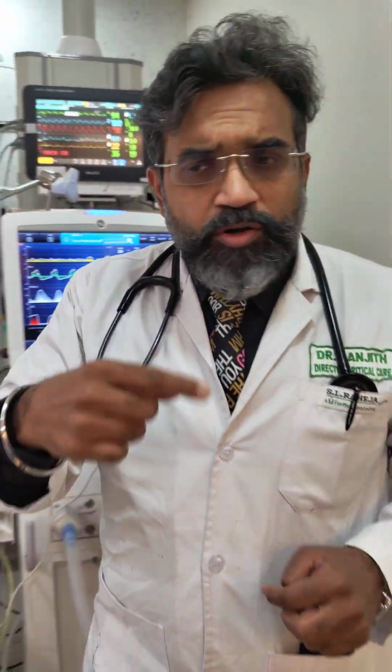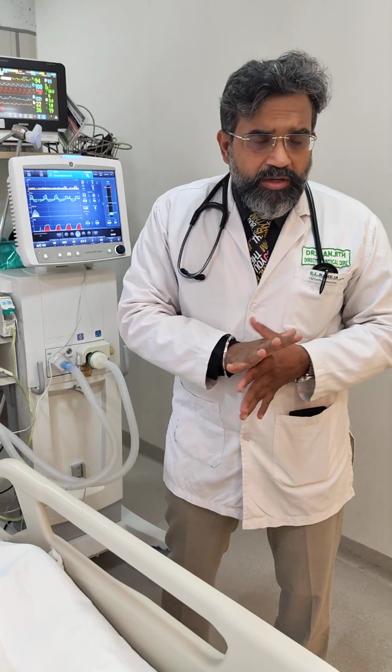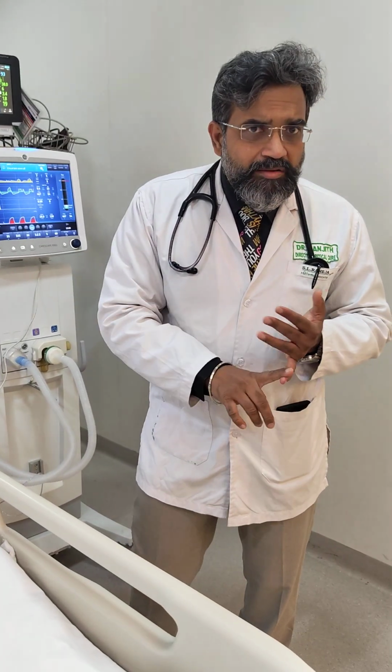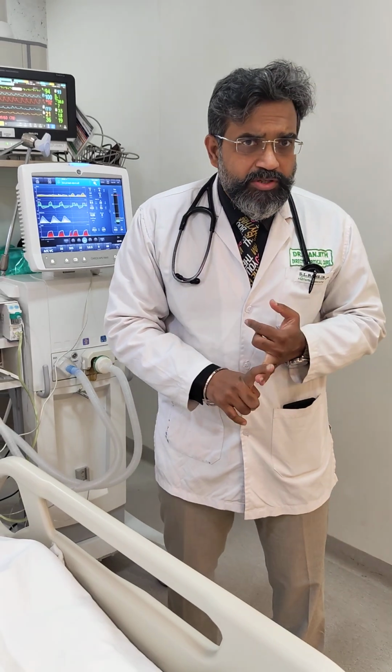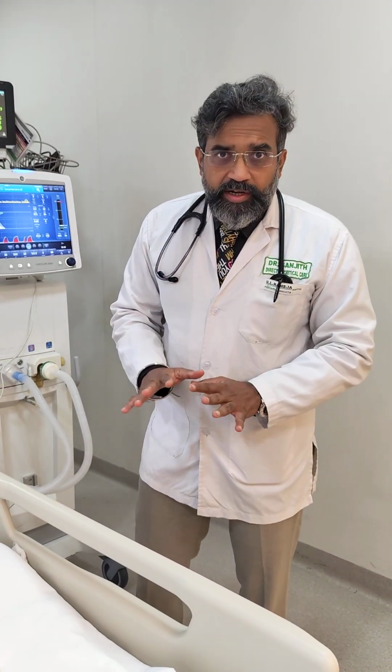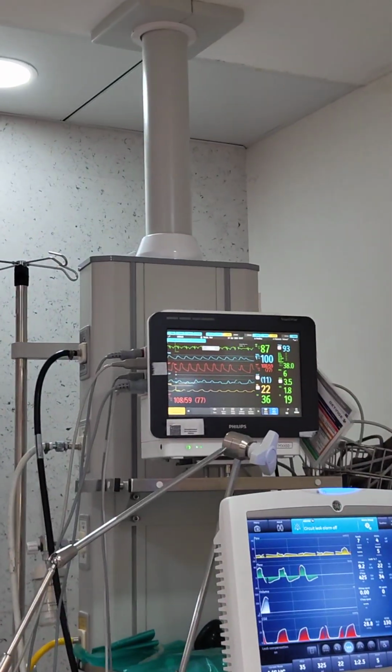This continuous cardiac output monitor is the one you need to have when you're doing passive leg raise. You cannot do passive leg raise using pulse pressure variation. You cannot do it using blood pressure. You cannot do it using CVP. It has to be flow. And the only monitor that gives you flow presently is the PiCCO monitor. That's what the cardiac output tells you: the flow.